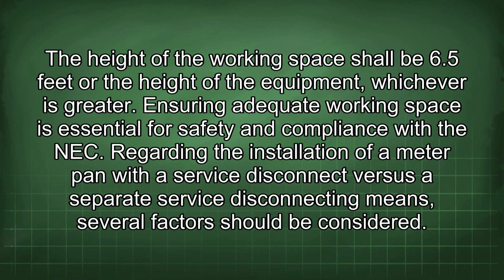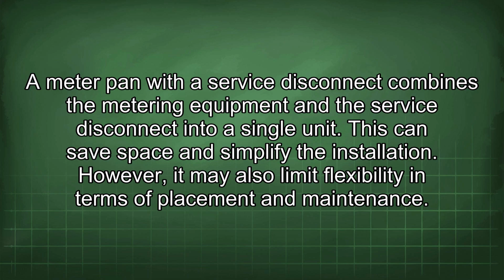The height of the working space shall be 6.5 feet, or the height of the equipment, whichever is greater. Ensuring adequate working space is essential for safety and compliance with the NEC. Regarding the installation of a meter pan with a service disconnect versus a separate service disconnecting means, several factors should be considered. A meter pan with a service disconnect combines the metering equipment and the service disconnect into a single unit. This can save space and simplify the installation.